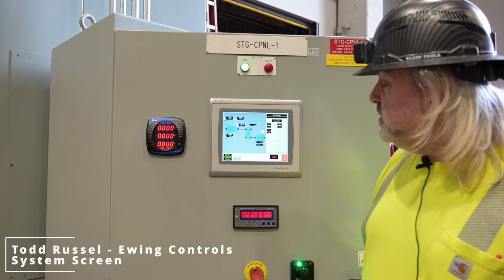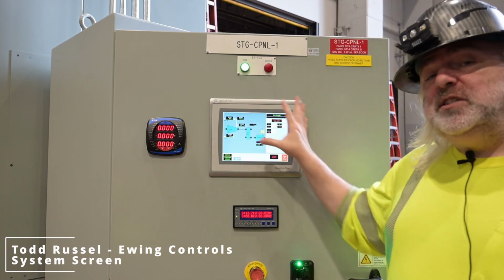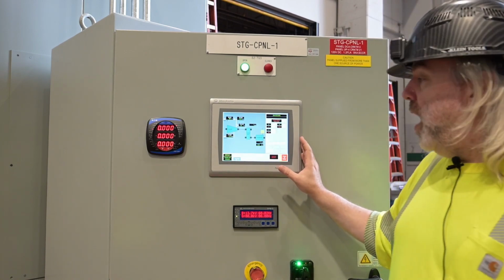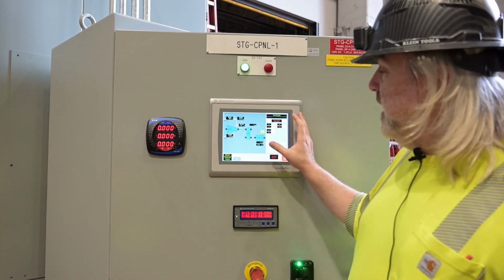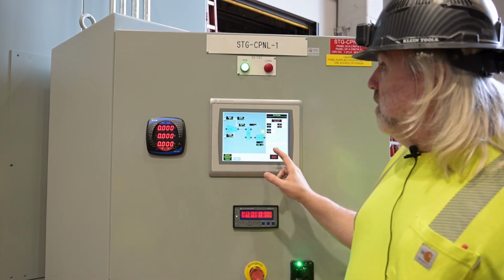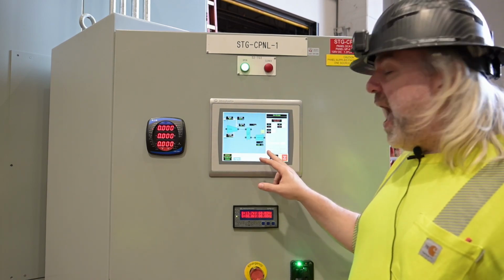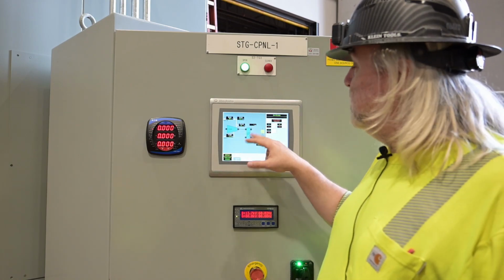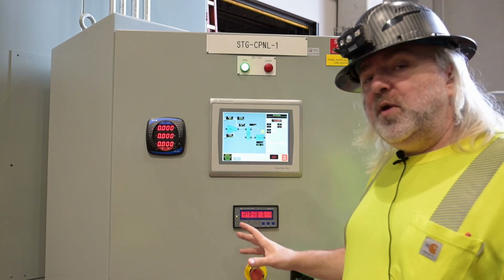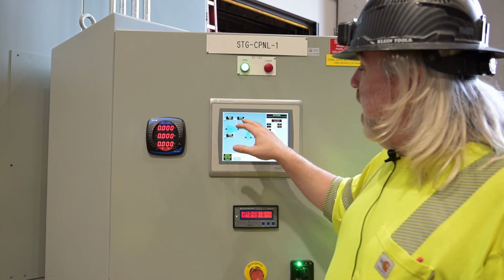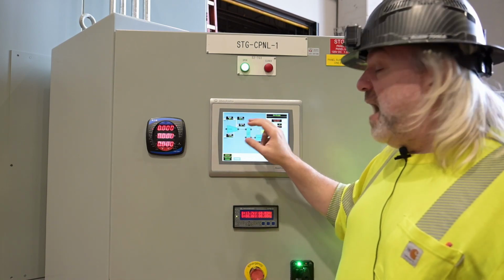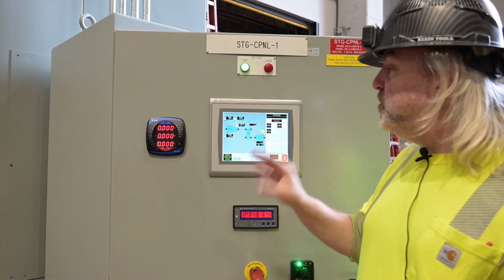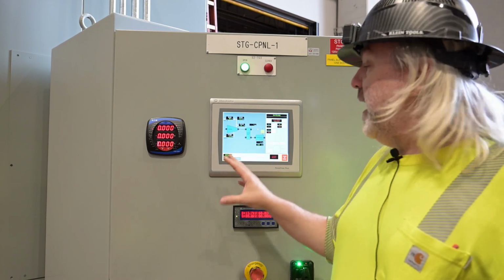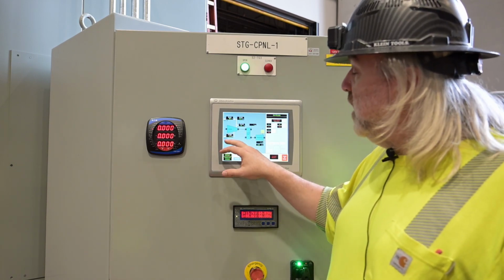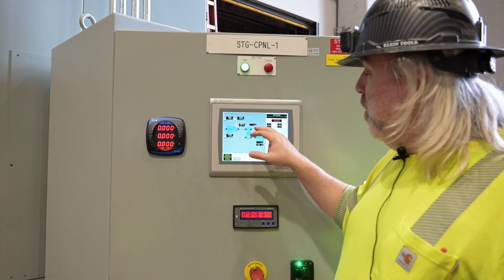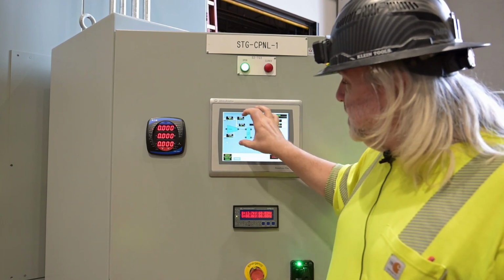Now, the next screen is our system screen. This is where you'll operate the system from. On the screen, we have a little visualization of the steam path of the system, plus some additional RPM, kW indication. We have our inlet pressure and temperature. We have our valve demand, not position, but what we want the valve to be. In addition to that, we have our exhaust pressure indication. So that's our steam side.